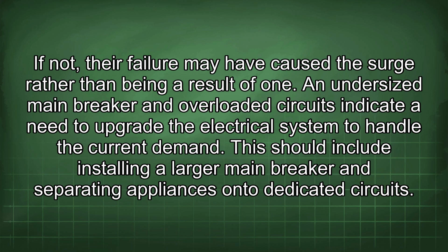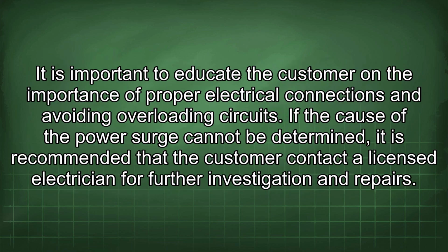An undersized main breaker and overloaded circuits indicate a need to upgrade the electrical system to handle the current demand. This should include installing a larger main breaker and separating appliances onto dedicated circuits. It is important to educate the customer on the importance of proper electrical connections and avoiding overloading circuits. If the cause of the power surge cannot be determined, it is recommended that the customer contact a licensed electrician for further investigation and repairs.